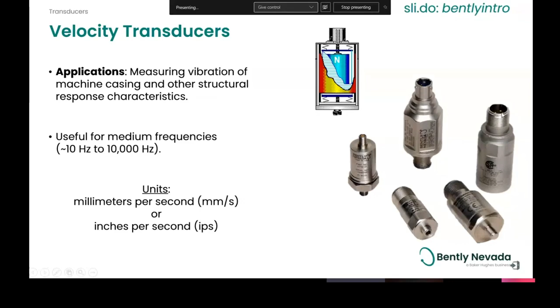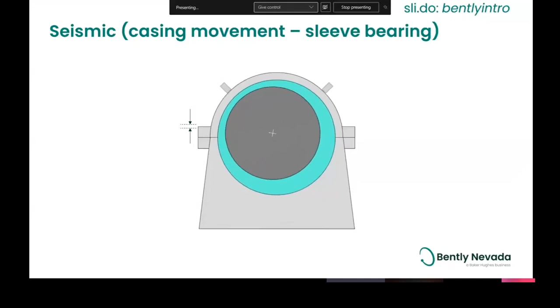So these are what we call velometers. And as mentioned before, the most typical application here is going to be machines where you're interested in the mechanical movement. So in this case, it's a sleeve bearing, but just due to the stiffness of the machine or the size or whatever, that casing is also moving. And if we aren't able to put a proximity probe on here, a velometer is basically going to be the next best thing. This would be one place where we recommend having velometers or seismoprobes.